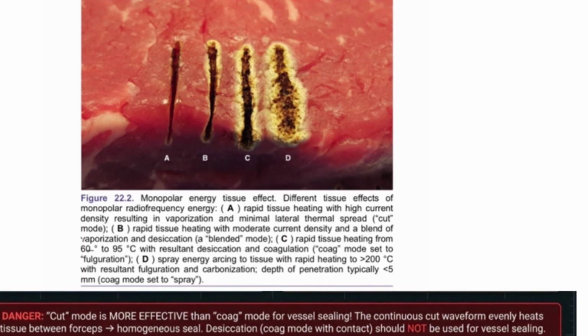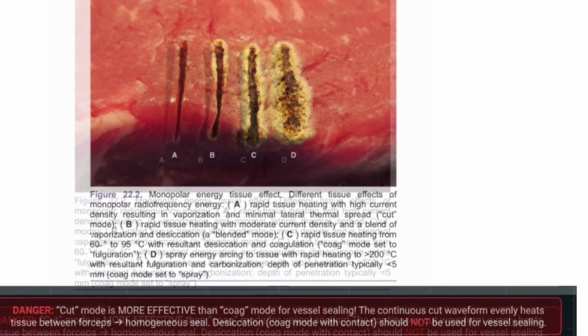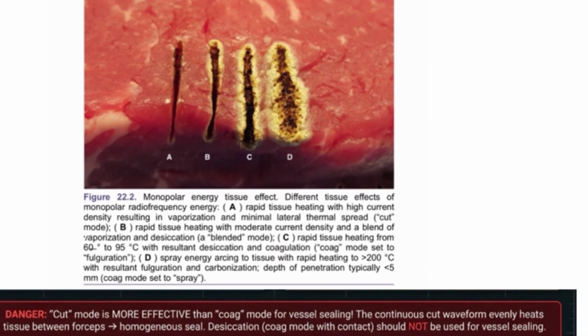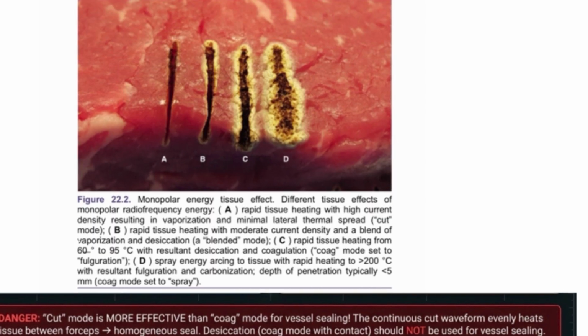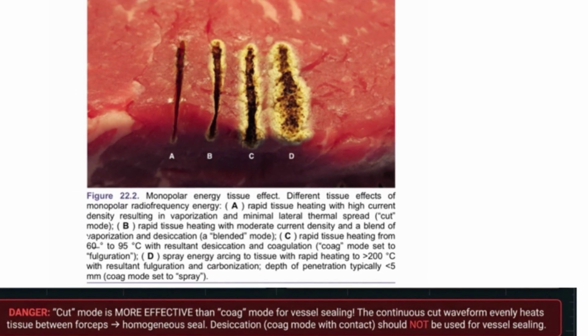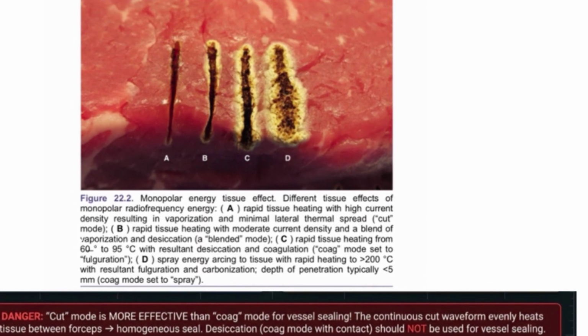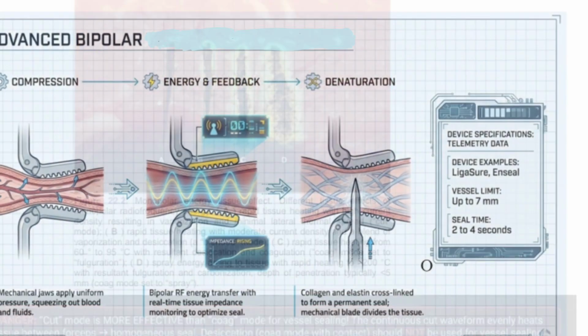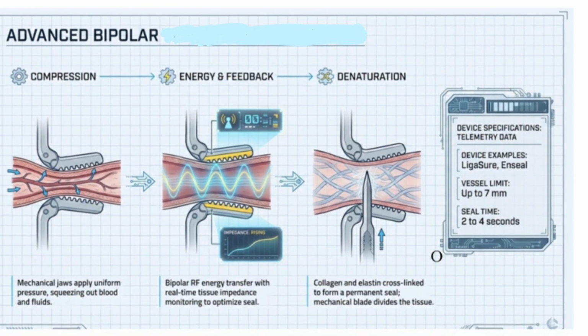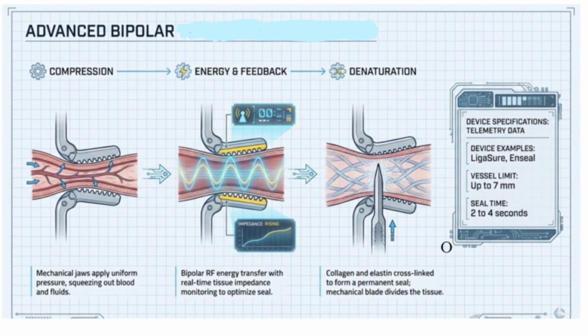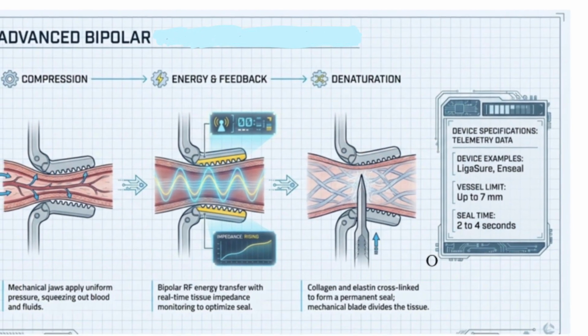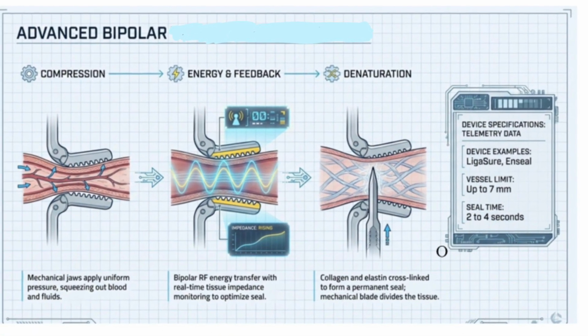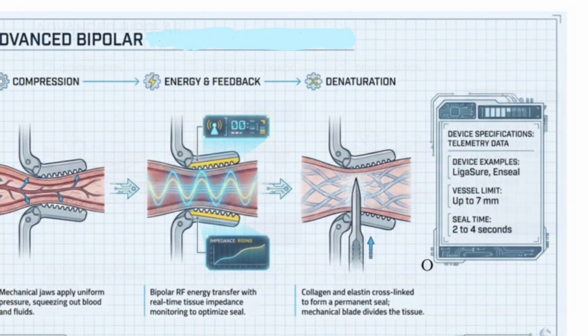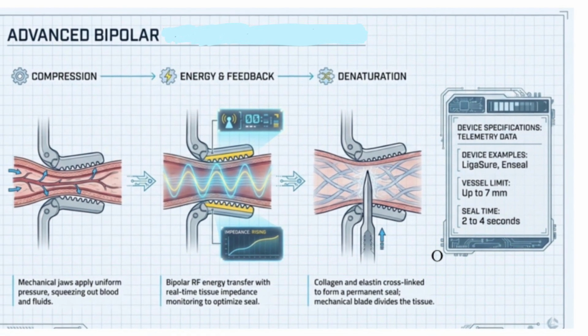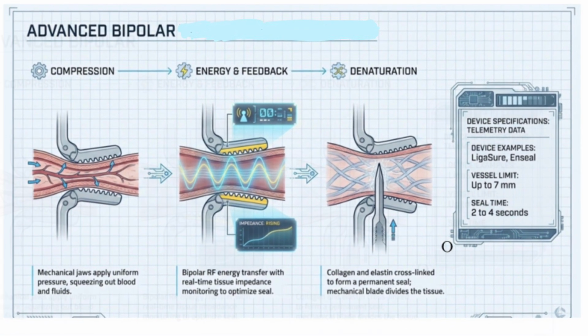The continuous cut waveform evenly heats tissue between forceps, producing a homogeneous seal. Desiccation. The coagulation mode with contact should not be used for vessel sealing. The advanced bipolar devices are the LigaSure and the EnSeal. They are useful in closure of the vessels of up to 7 mm size. The sealing time is 2 to 4 seconds.